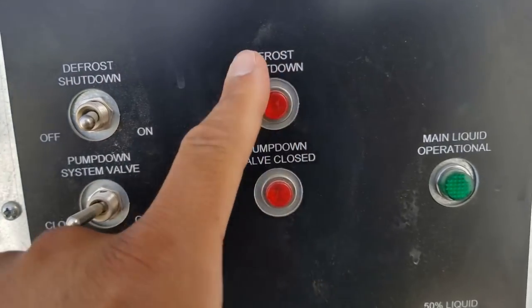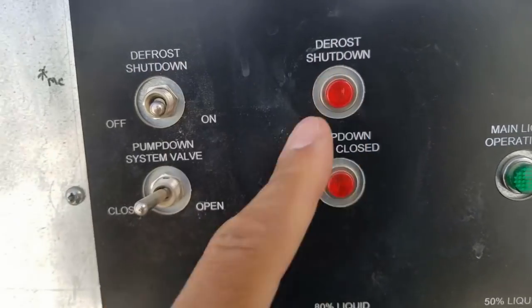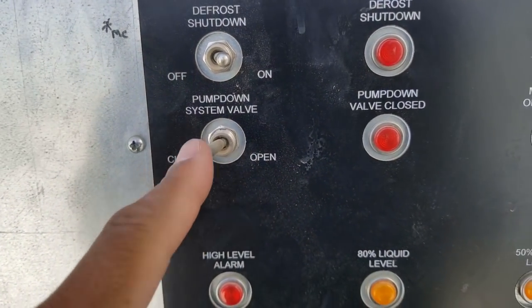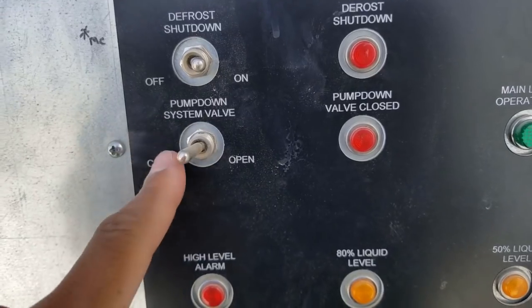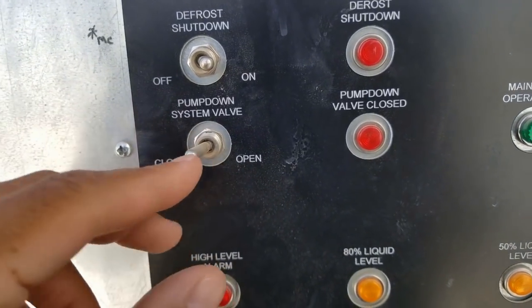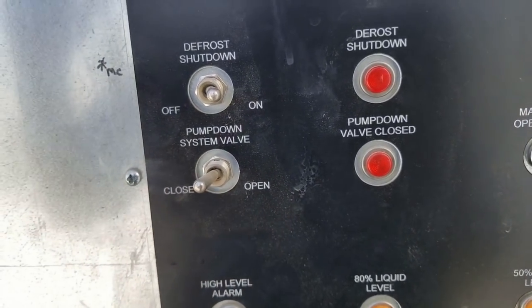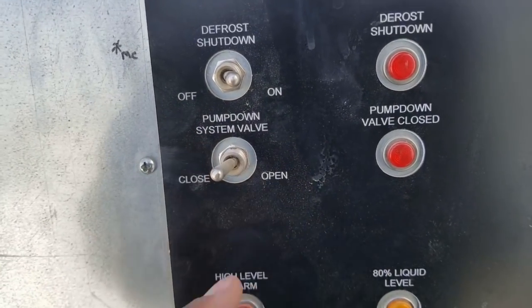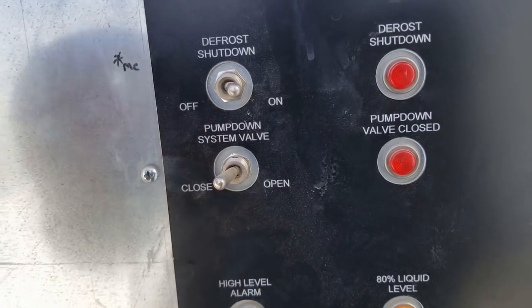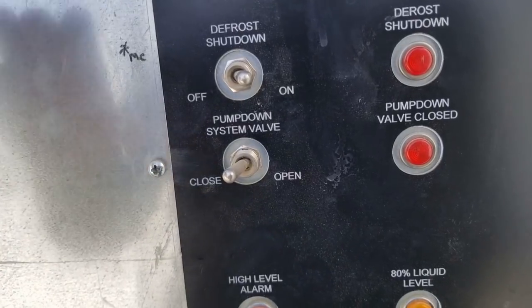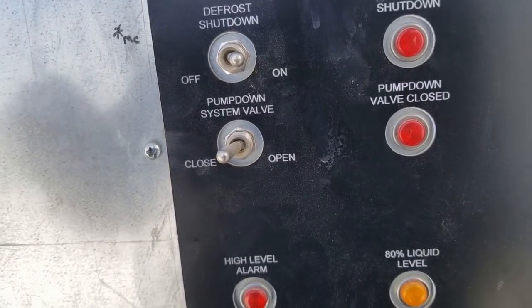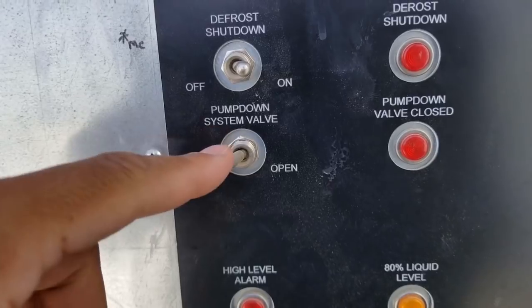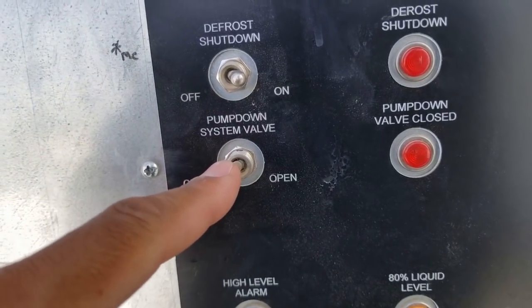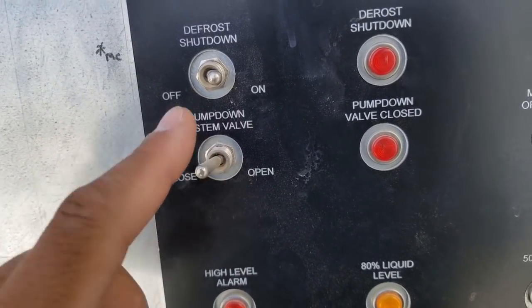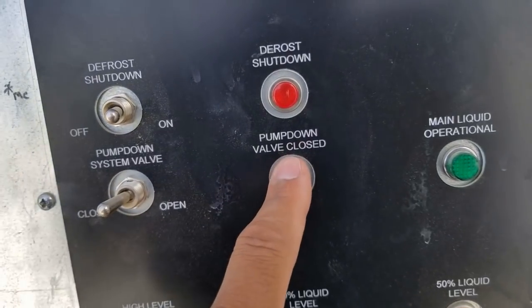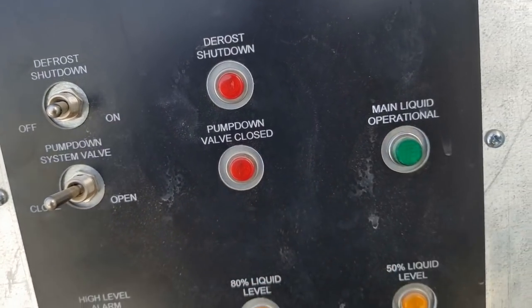So defrost shutdown, that's the light for this. Your pump valve, so right now it's closed, which is the switch is closed. You don't want it to be. Once you open the switch, then it shuts down all the solenoids to the cases and it starts pumping down the rack. So that's for service or something like that if you want to do that. And this is just your light right here and your main liquid operational.